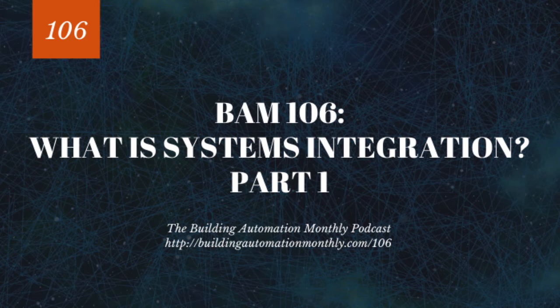And you want to go and add BACnet devices that are also on this trunk. Actually, the PX is a bad example because that's IP based in most scenarios. Okay, let's say you've got Johnson Controls FECs. Not their new FECs that are IP based, or FACs, but the older ones that are MSTP based. So you've got these, and let's say that, for whatever reason, a new facility director comes in and he's like, I don't like those.